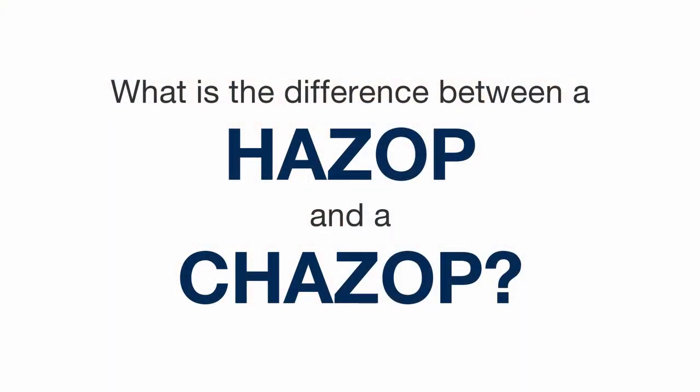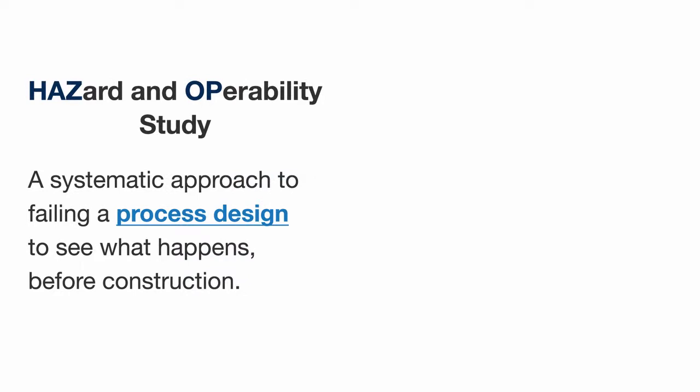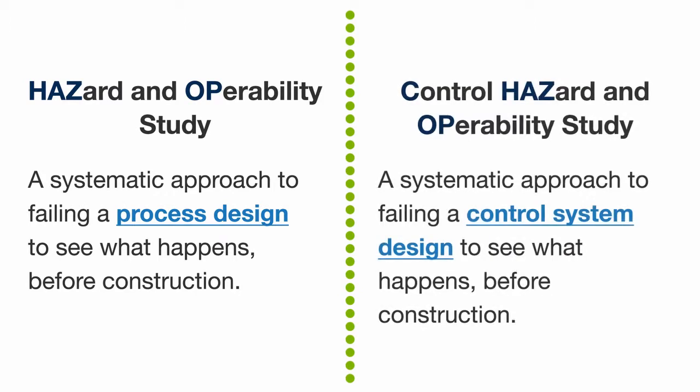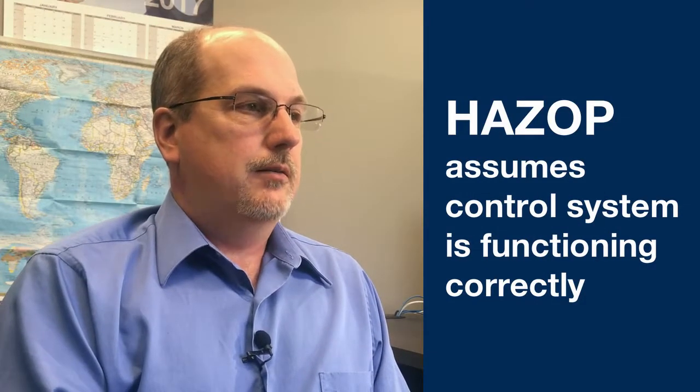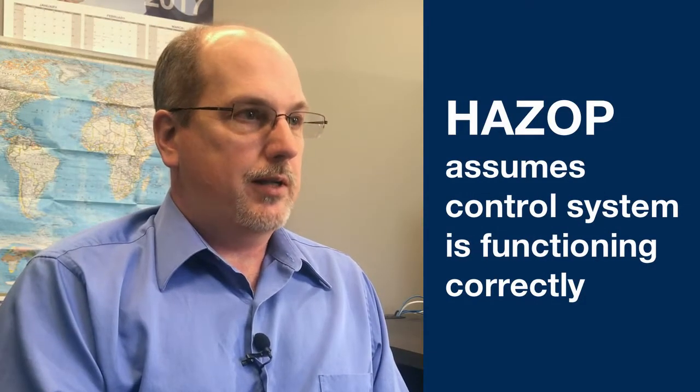The difference between a HAZOP and a CHAZOP really is the focus. A HAZOP looks at the entire facility — the mechanical equipment and the process — where a CHAZOP looks at the control system itself. A HAZOP typically assumes that the control system is operating correctly, whereas a CHAZOP goes into the control system and fails individual components.